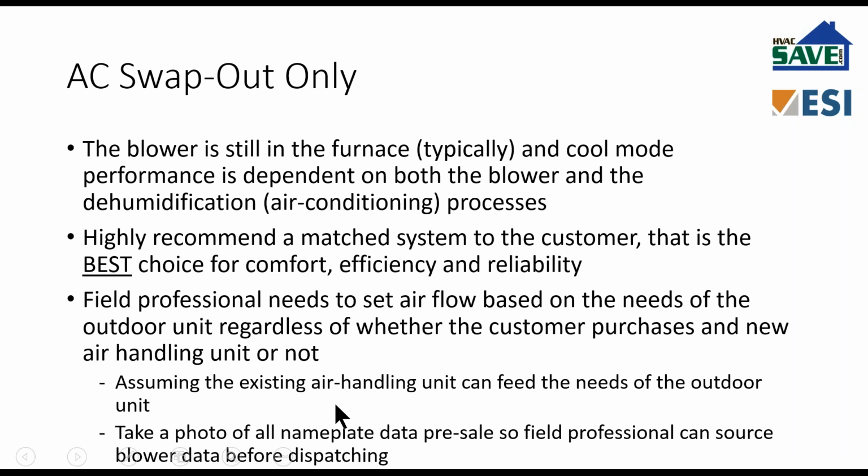We run into situations where it's an AC swap out only, and there's just no way that the existing furnace can give the outdoor unit the airflow that it needs. Recommend on a pre-sale basis that you take a picture of all nameplate data on everything, indoor unit, outdoor unit, furnace, so that in the event you cannot persuade the customer to buy a new matched blower to go with that air conditioner, you can at least provide the field professional a manufacturer name and model number for that furnace so they can go source those blower charts before they dispatch.